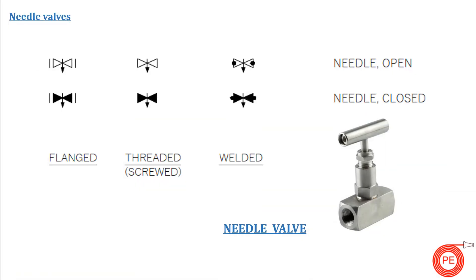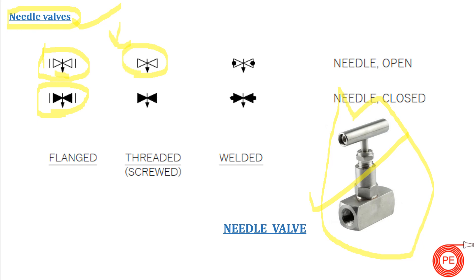The next and last valve for today's video is the needle valve. Needle valves are used in instrumentation applications or where a tight shutoff is required, mainly in hazardous service where you can't allow leakage. This is how a needle valve looks: there is a downward-pointing arrow as the symbol. Most designers don't change the symbol for needle valves. Blackish fill inside means closed, hollow means open; two lines beside means flanged, nothing means threaded, and two dots means welded connection.